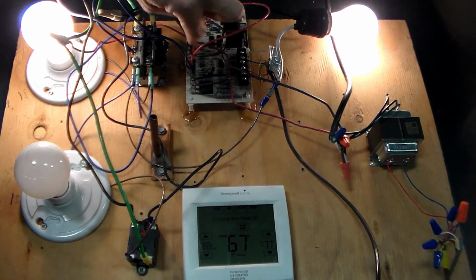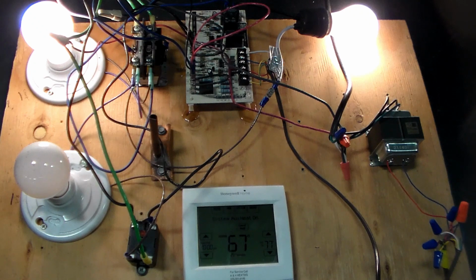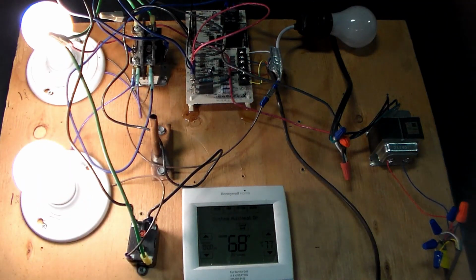And this defrost sensor then comes loose, well, doesn't come loose, but the ohms go back high again. It's an NTC thermistor or a snap disc. So it'll either open when the coil warms up to 55 degrees or the ohms will go really high from it being a thermistor. Either way, that's how it tells the board that it's defrosted. And if that doesn't happen within 10 minutes, then the timing of the board will switch it back to normal mode after 10 minutes.